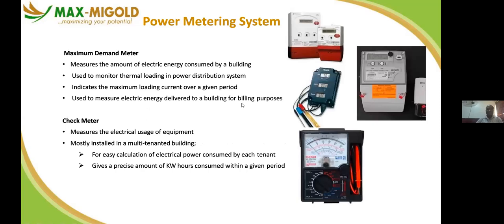We have different types of metering systems. We have the maximum demand, and the check meter. The maximum demand is mostly used for commercial buildings where a large amount of energy is required. So use maximum demand there. They are used to monitor thermal loading in power distribution stations. So you can use it for so many things. We have the check meter, which measures the electrical use of equipment, mostly installed in multi-tenanted buildings. Those are the small meters that you bill your customers with, those who live in multiple buildings, where you have many tenants coming together. You use the check meter to get their consumption, and you bill them accordingly.